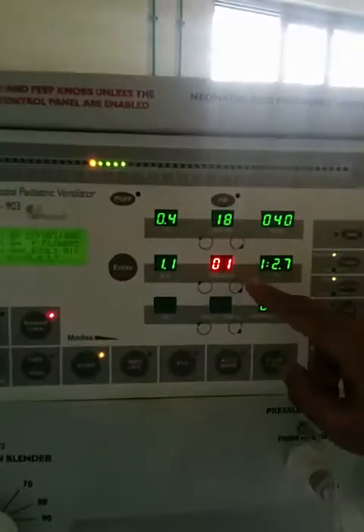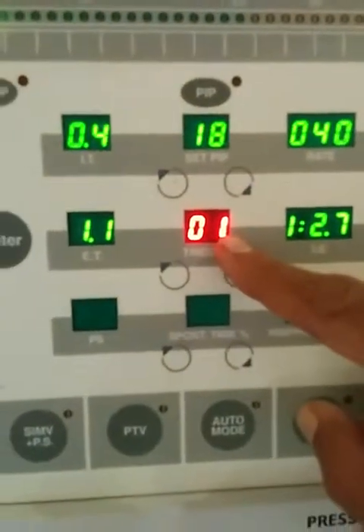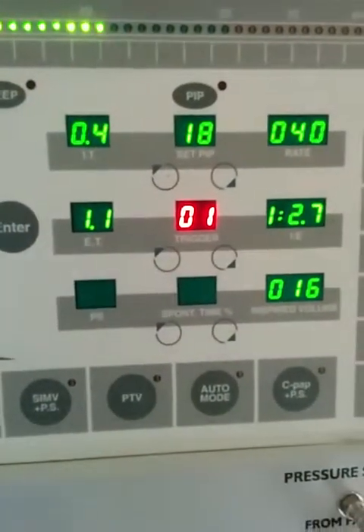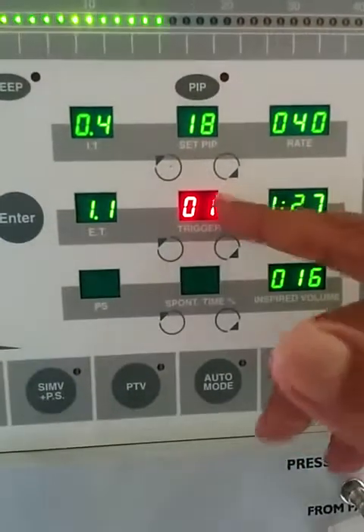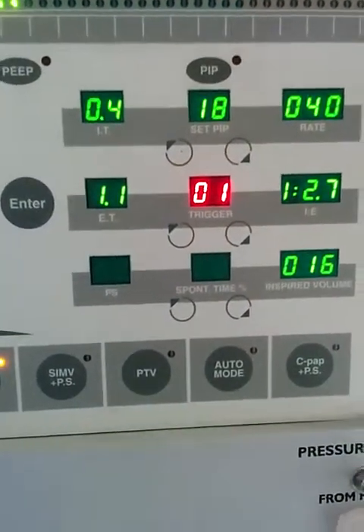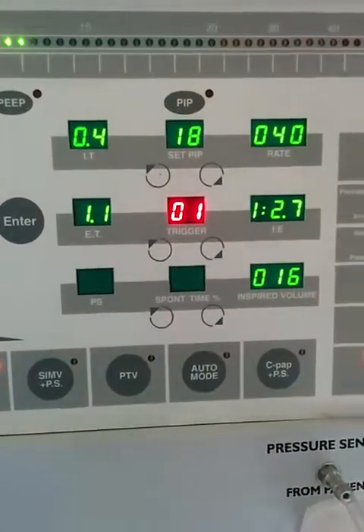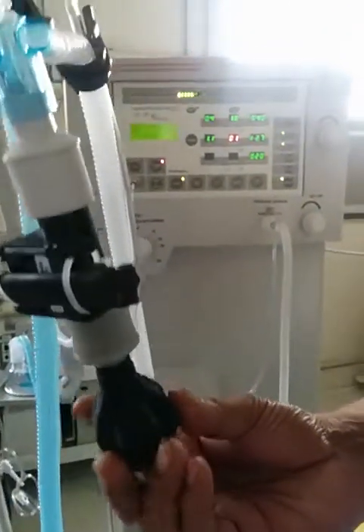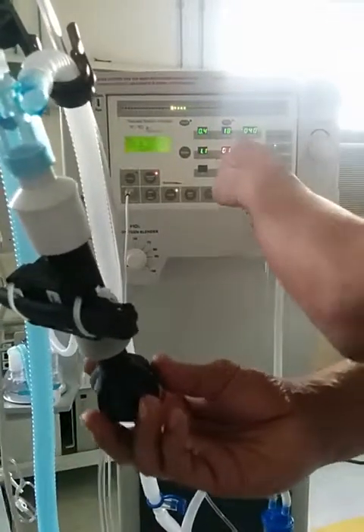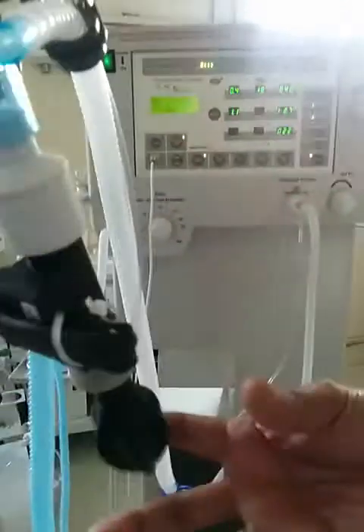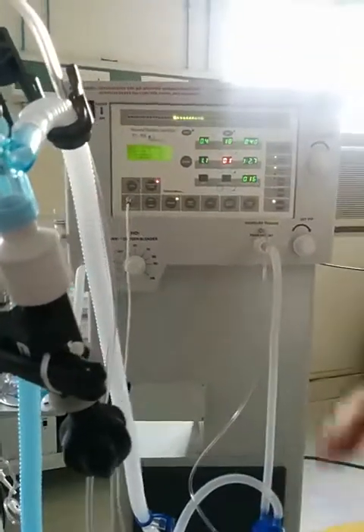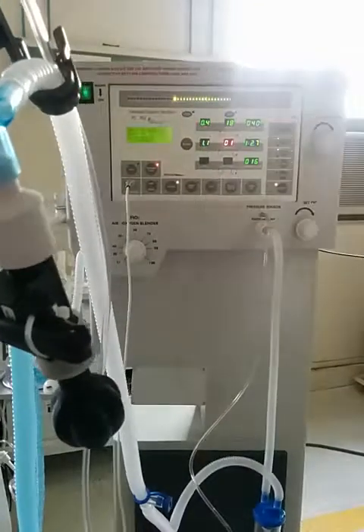And importantly, we have to set the trigger level. This is the trigger level. If the patient breathes, and the pressure in the breathing circuit is reduced during the expiration time by 1 centimeter of water column, the machine will sense a breath and it will give an assisted breath to the patient. I'll show it to you by pressing this. See. When the patient triggers the machine, the display will flash and an assisted breath will be given to the patient. Always ensure that the trigger level is kept at a very low level so that the patient can easily trigger the machine and can get an assisted breath.